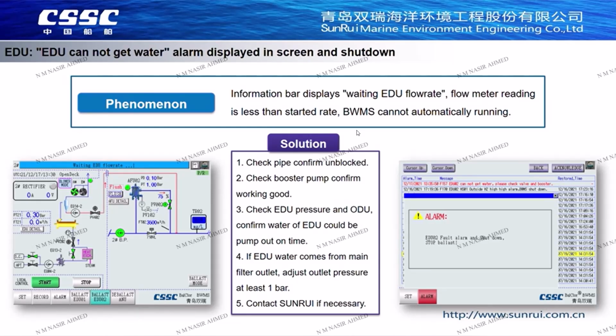To deal with this fault, the first point is to check whether EDU inlet and outlet pipe are blocked. Second, check whether the boost pump works normally, and suction and discharging pressure are normal. The third is to check the EDU internal pressure and the dosing unit. Confirm the treated seawater in EDU buffer tank can be pumped out in time.